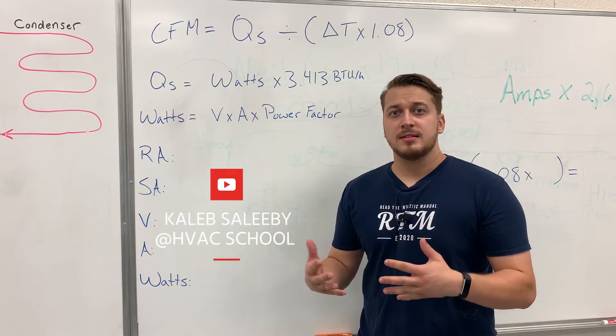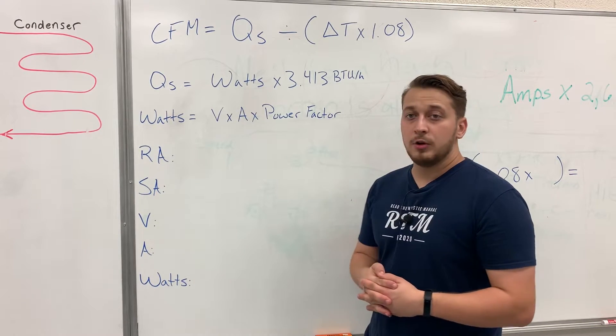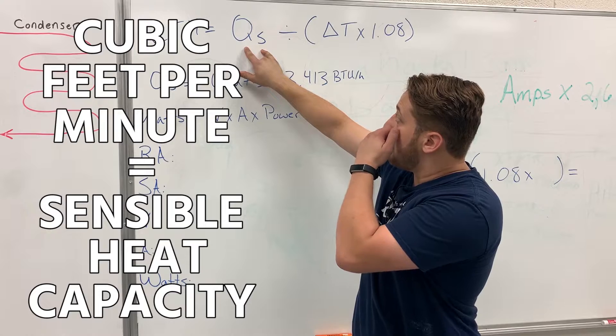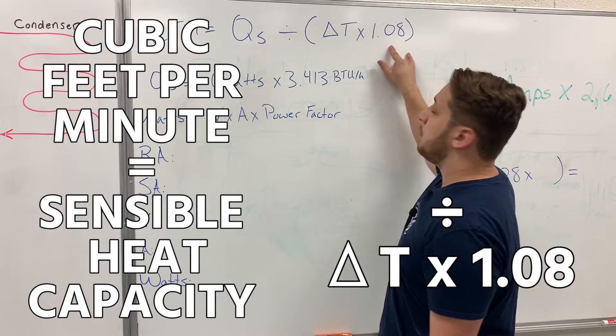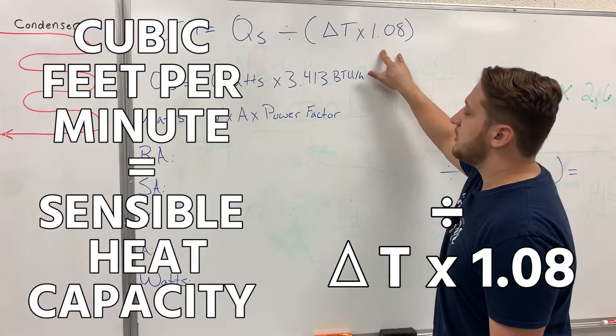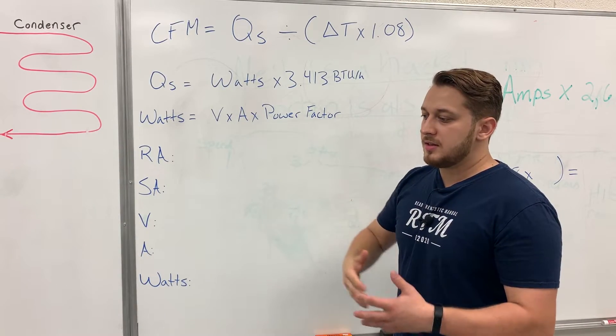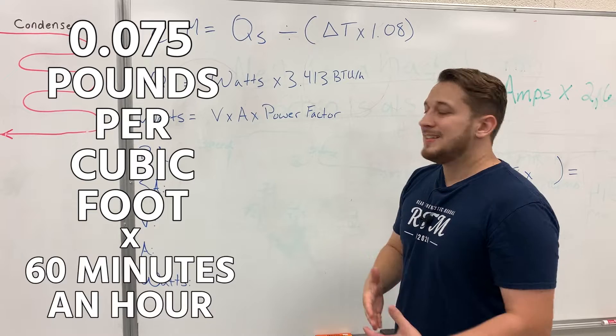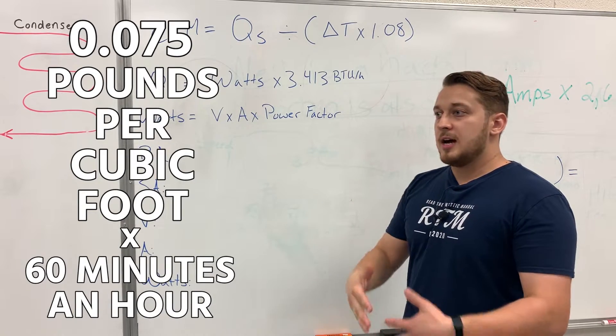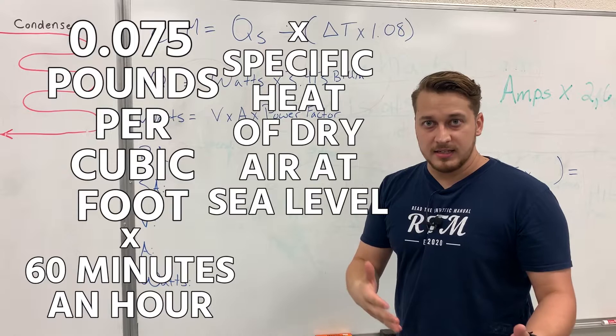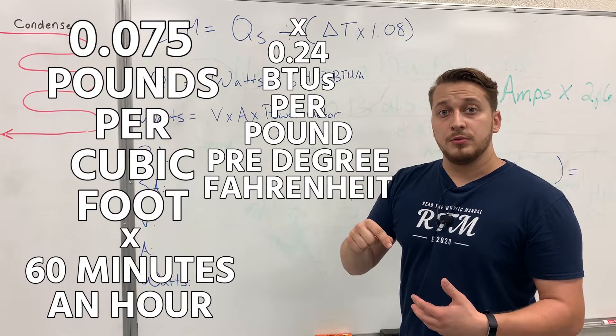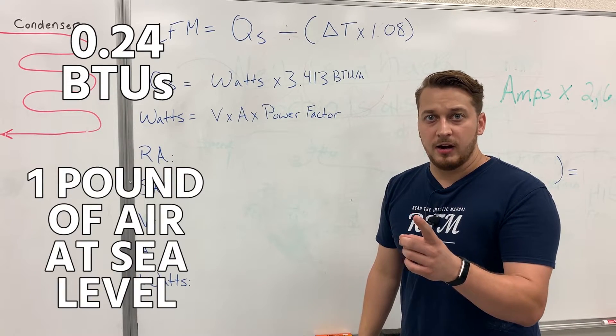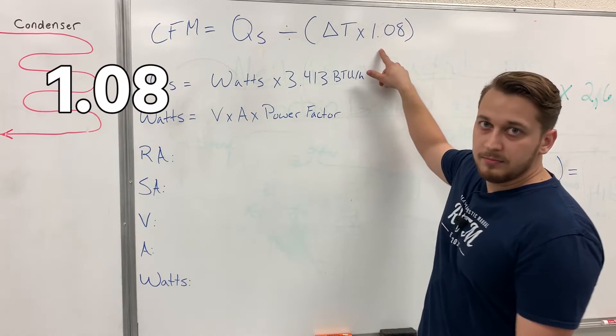We're going to take a look at the heat rise calculation for airflow. The formula is: CFM (cubic feet per minute) equals sensible heat capacity divided by delta T times 1.08. The 1.08 comes from a separate formula: air density at sea level (0.075 lb/ft³) times 60 minutes per hour times the specific heat of dry air (0.24 BTUs per pound per degree Fahrenheit). So it takes 0.24 BTUs to heat one pound of air one degree Fahrenheit — that's how we get 1.08.